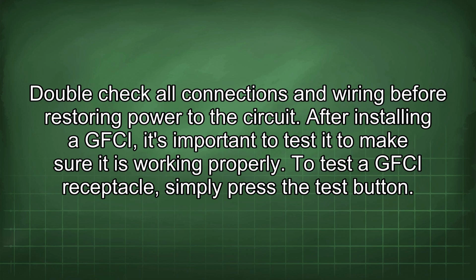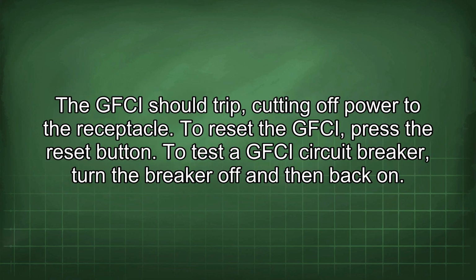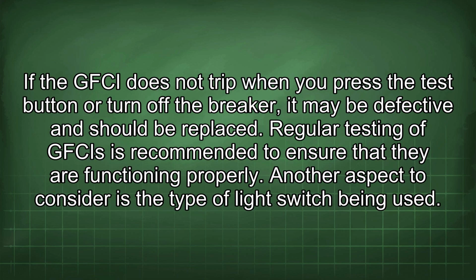After installing a GFCI, it's important to test it to make sure it is working properly. To test a GFCI receptacle, simply press the test button. The GFCI should trip, cutting off power to the receptacle. To reset the GFCI, press the reset button. To test the GFCI circuit breaker, turn the breaker off and then back on. If the GFCI does not trip when you press the test button or turn off the breaker, it may be defective and should be replaced. Regular testing of GFCIs is recommended to ensure that they are functioning properly.